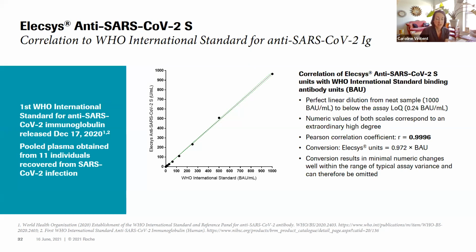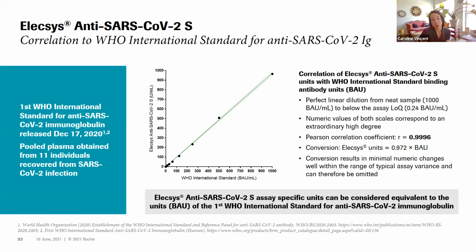0.9996. So basically the conversion of the Elecsys units to the international standard units results in really minimal numeric changes that are well within the range of typical assay variance, and therefore the application of a conversion factor is not required, and the Elecsys units can be considered equivalent to the units of this new international standard. This data will be included in the next version of our package insert for this assay.